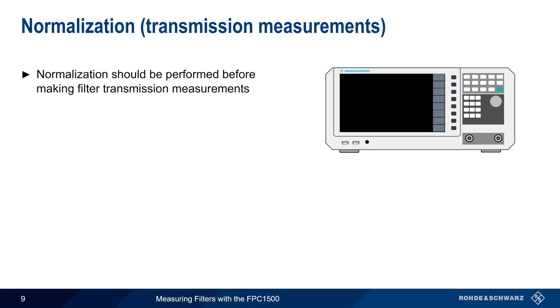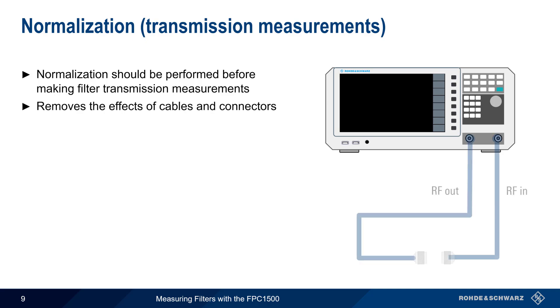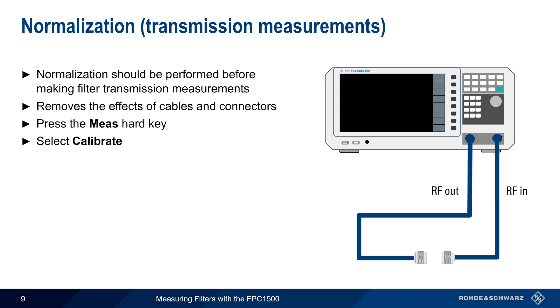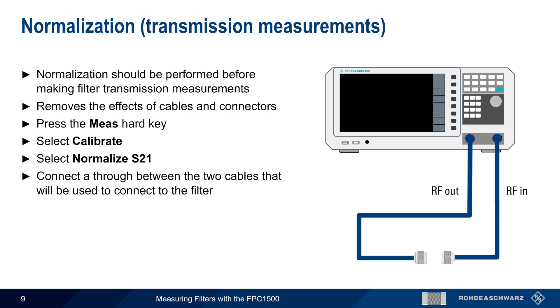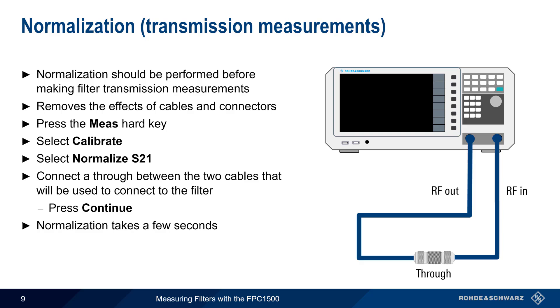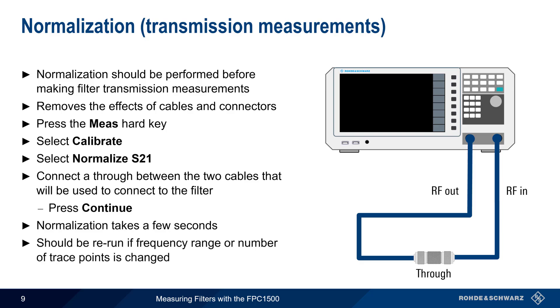A very important part of any transmission measurement is normalization, and this should be performed before making any filter measurements. Normalization can remove or reduce the effects of cables and connectors on the measurements. To run normalization, press the Measure hard key, select Calibrate, and then Normalize S21. A through should be connected between the cables that will be attached to the filter. After pressing Continue, normalization will complete in a few seconds. For the best accuracy, normalization should be rerun if the frequency range or number of trace points has been changed.